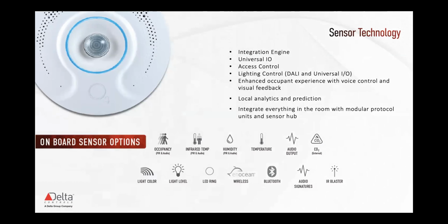We started the project with CO2 sensing built in, but then found out that ASHRAE standards say CO2 has to be read from, I believe, a 4-foot or maybe 5-foot level, and since this is ceiling mounted, that didn't really work. So for CO2, we instead use a Delta branded EnOcean CO2 sensor, which is wall mounted in that case.